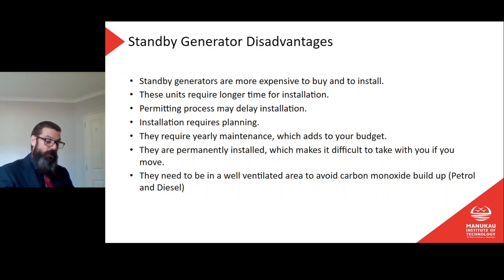For large backup generators like those running hospitals, they might face days or even weeks without fuel delivery, so they need the ability to store enough fuel to run for that period - running into the thousands of litres. Are you going to change out thousands of litres of fuel every 6 months? If you have 20,000 litres of diesel, that's about $30,000 worth of fuel you'd swap out every 6 months. Nobody wants to pay for that. There will be a hell of a lot of other options available that cost less than $30,000 every 6 months.